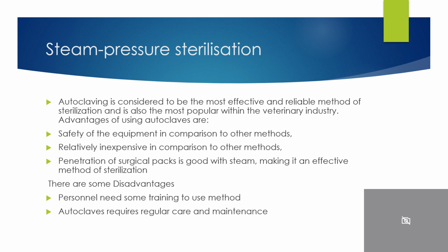Steam pressure sterilisation. Autoclaving is considered to be the most effective and reliable method of sterilisation and is also the most popular within the veterinary industry. Advantages of using autoclaves are safety of the equipment in comparison to other methods. Penetration of surgical packs is good with steam, making it an effective method. There are, however, some disadvantages. Personnel will need some training in order to be able to use the method appropriately, and the autoclave requires regular care and maintenance.